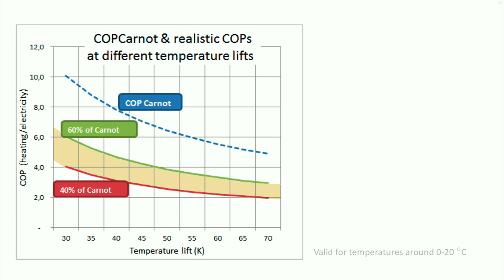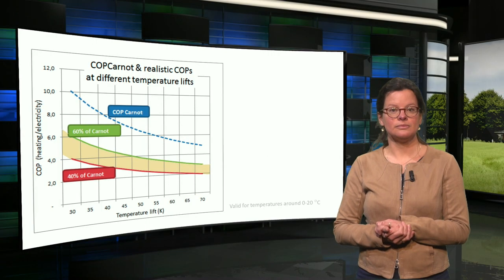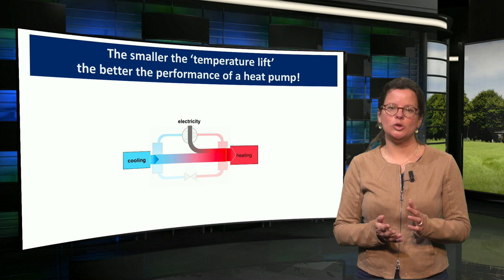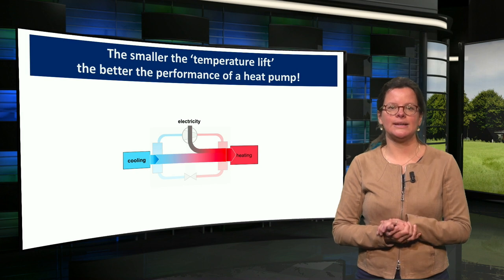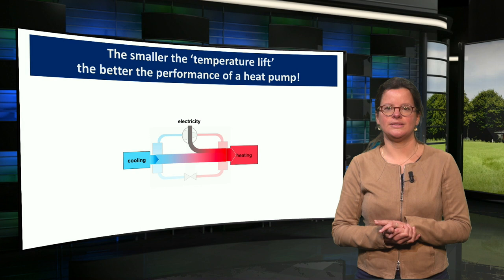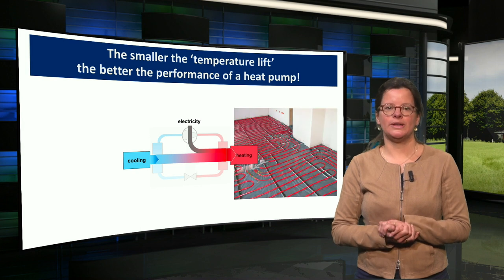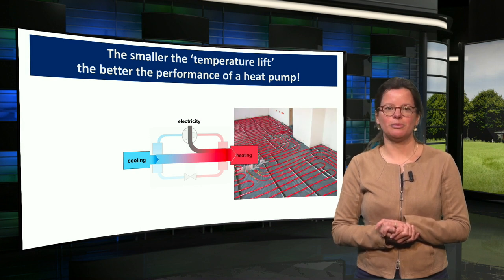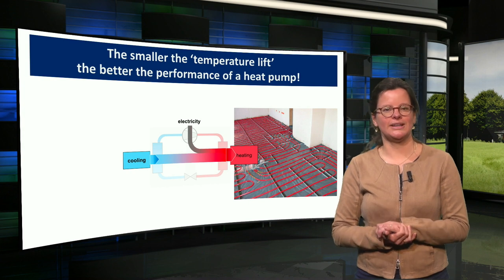As can also be seen from this figure, it is very favorable to minimize the temperature lift needed. To achieve this, we aim for low temperature heating and high temperature cooling, for example by using floor heating or low temperature radiators and by finding sources with a favorable temperature, which brings us to the next topic.